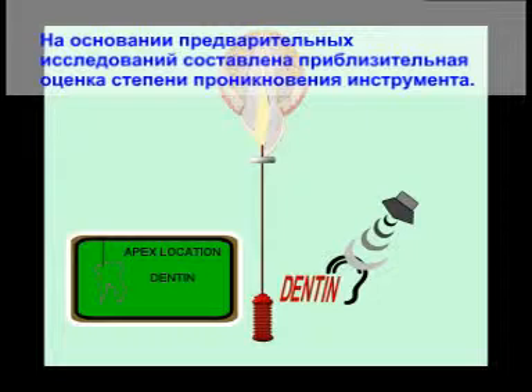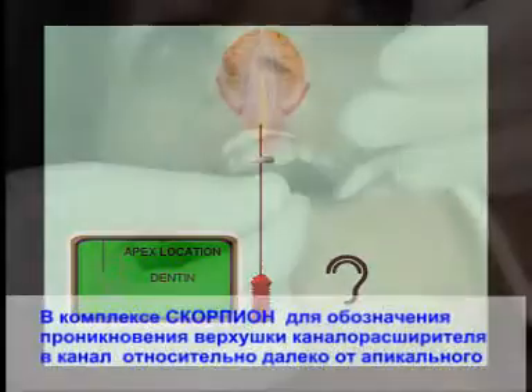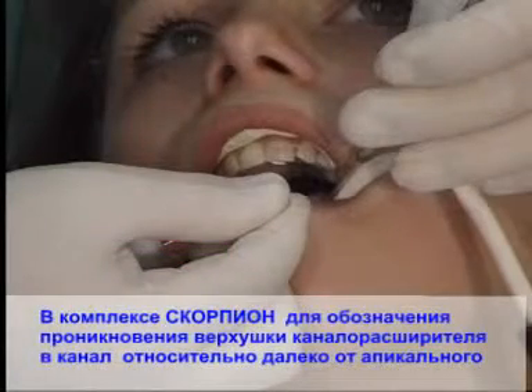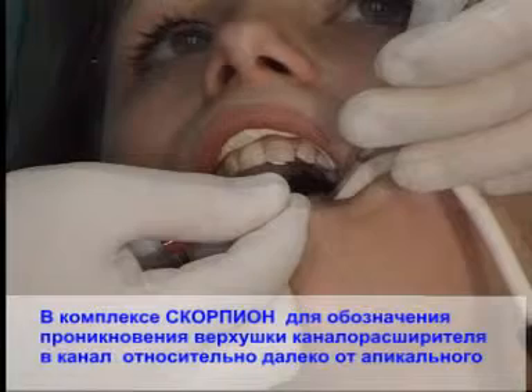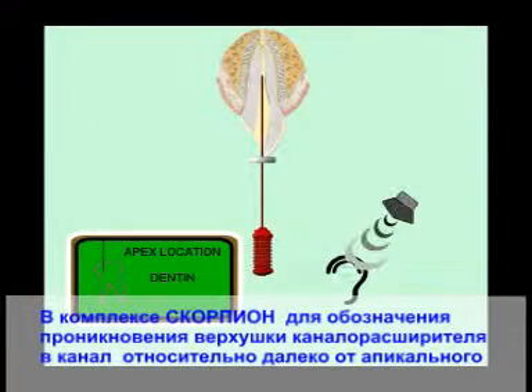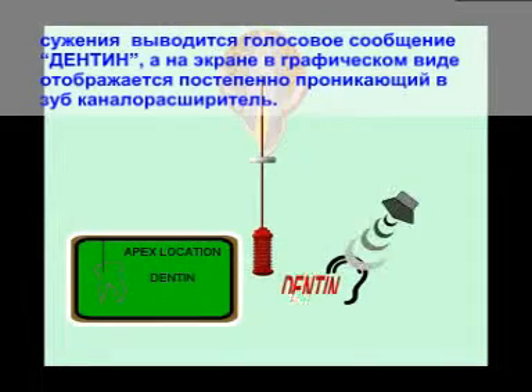An approximate assessment of the instrument penetration degree has been done on the basis of preliminary research. In the Skorpion set, top canal widener penetration in the canal, comparatively far from the apical narrowness, is indicated by an oral message "dentin", and a canal widener gradually penetrating in a tooth can be seen on the screen.